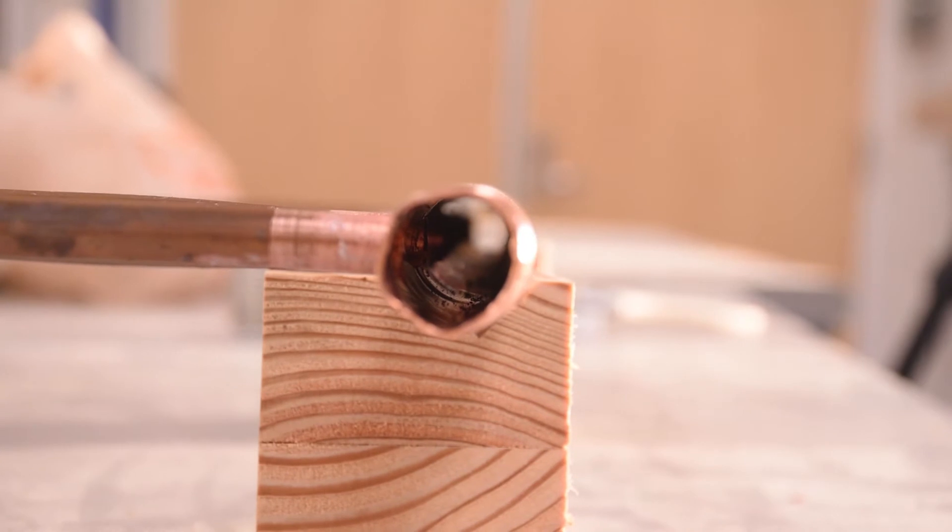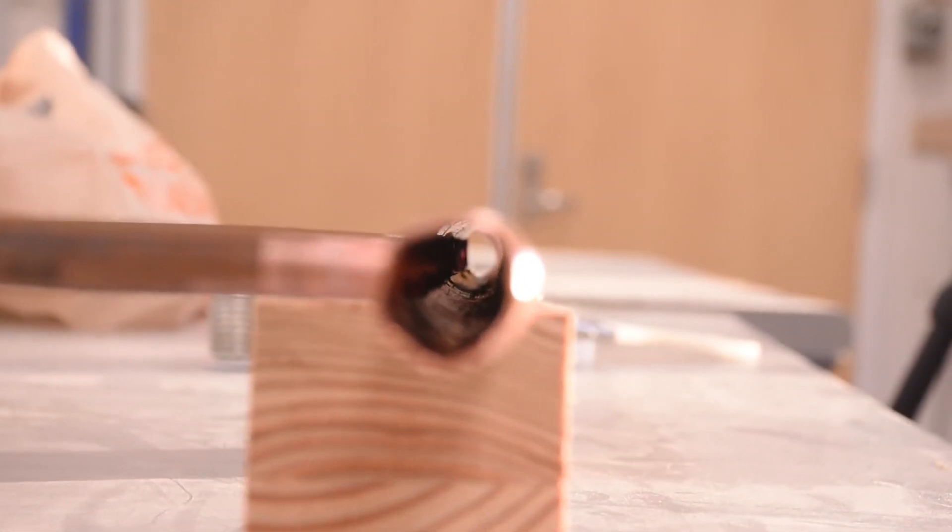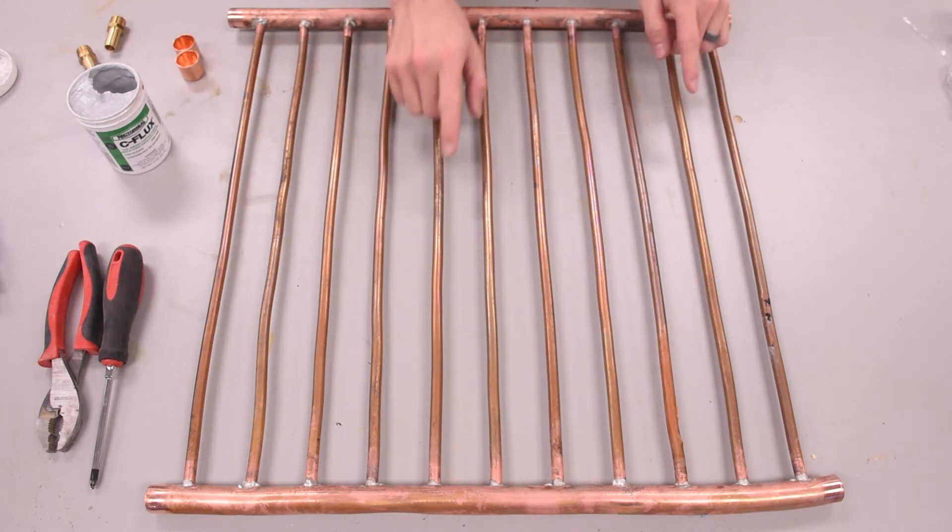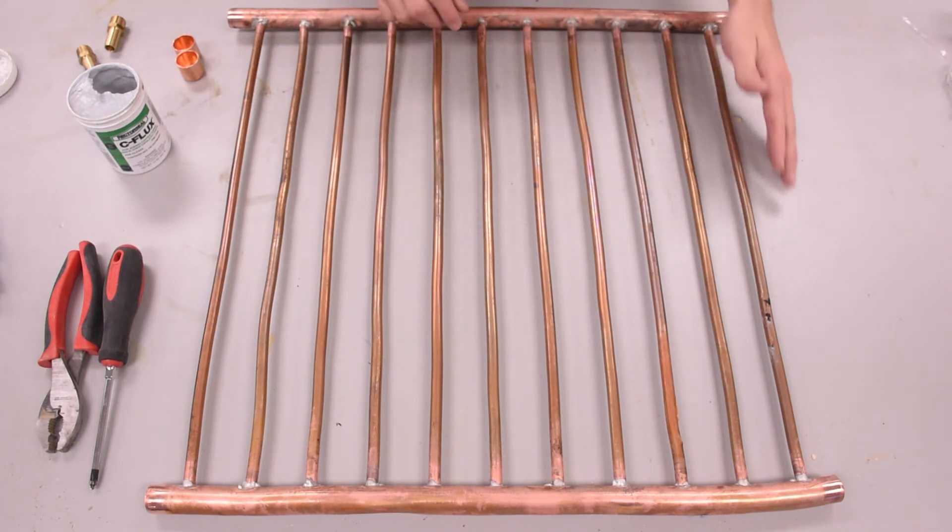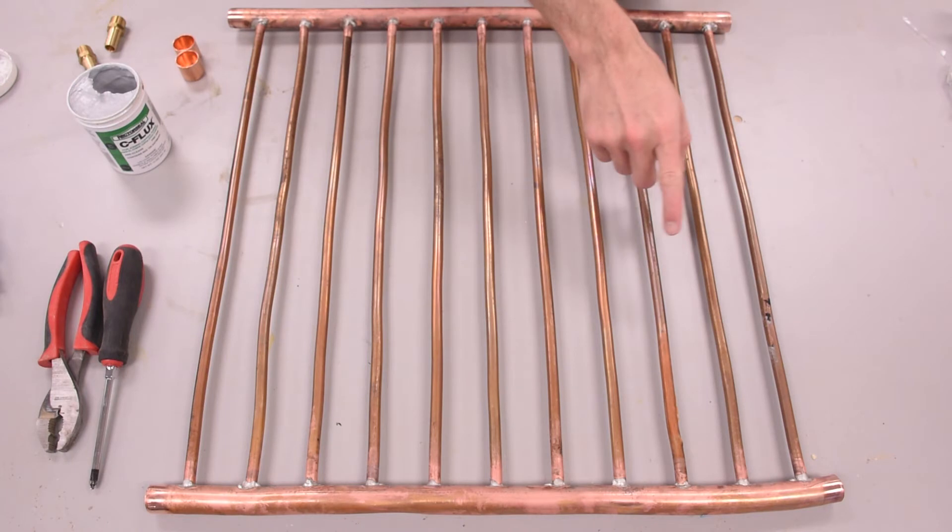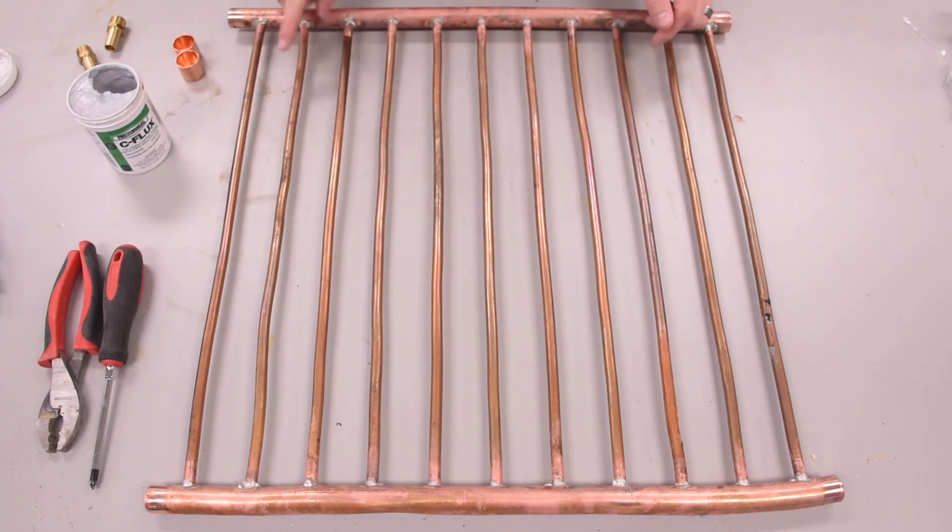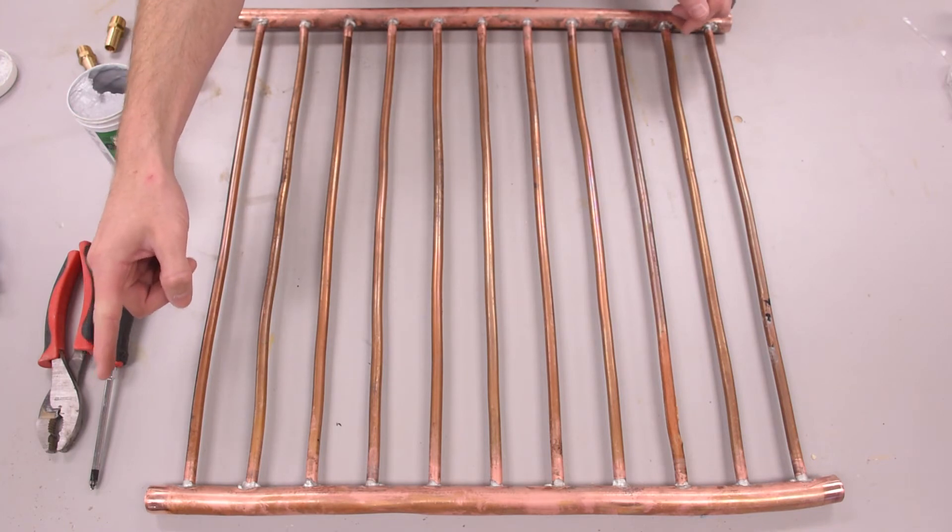I had to go back here and reheat this spot to remove it. Here you can see the camera focus dot inside the header, along with all the tube ends firmly in place. I want the chilled water to flow from the bottom to the top because natural convection will reduce some of the load on the pump. I also want the inlet and outlet on the opposite ends so that the entire tube field gets utilized and all the water travels the same distance from the inlet to the outlet.